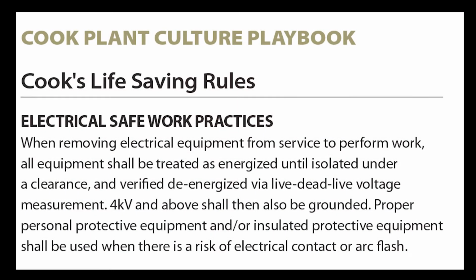When removing electrical equipment from service to perform work, all equipment shall be treated as energized until isolated under a clearance and verified de-energized by a live-dead-live voltage measurement. 4 kV and above shall also be grounded. Proper personal protective equipment and/or insulated protective equipment shall be used when there is a risk of electrical contact or arc flash.